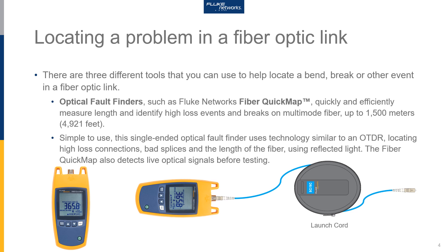You can see high loss events, high reflective events, and you can even locate breaks on the fiber. These tools are simple to use — it's a single-ended optical fault finder that uses technology very similar to that of an OTDR, allowing you to locate high loss connections, bad splices, and check the length of the fiber. Because they use reflected light, they see all the events down the fiber, and if your fiber is still active, it will indicate that you've connected the tool to an active fiber.